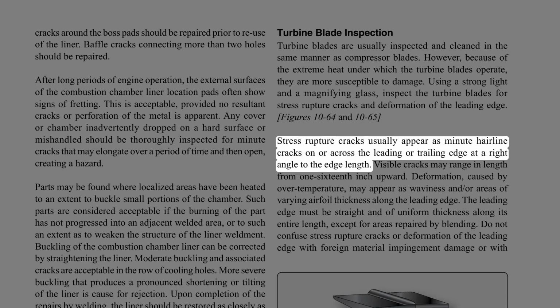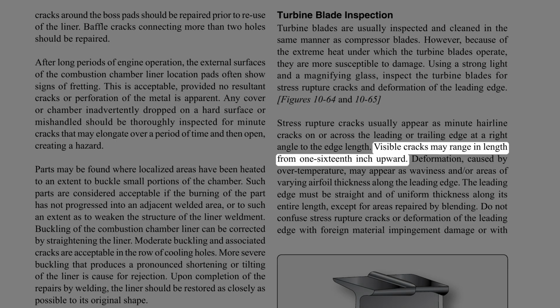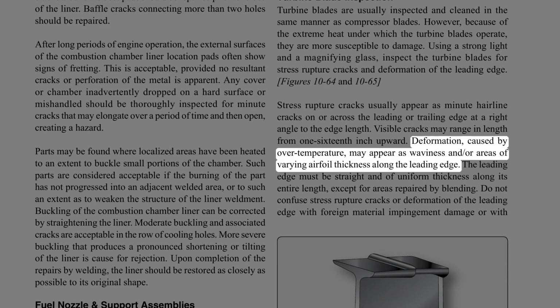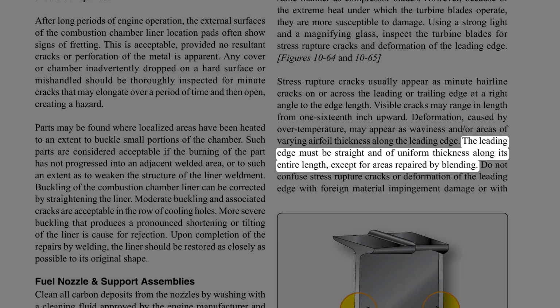Stress rupture cracks usually appear as minute hairline cracks on or across the leading or trailing edge at a right angle to the edge length. Visible cracks may range in length from 1/16 inch upward. Deformation, caused by over-temperature, may appear as waviness and/or areas of varying airfoil thickness along the leading edge. The leading edge must be straight and of uniform thickness along its entire length, except for areas repaired by blending.